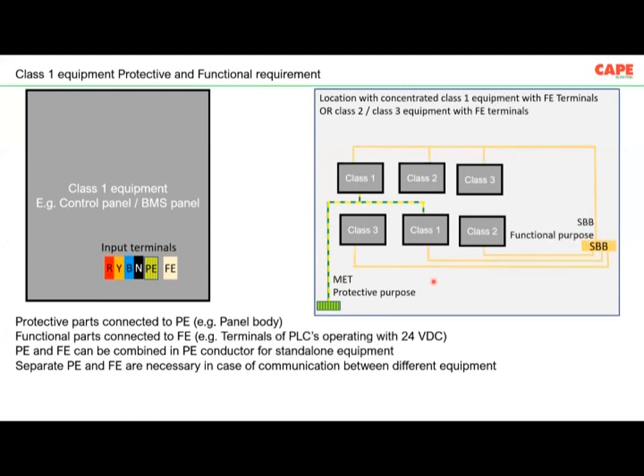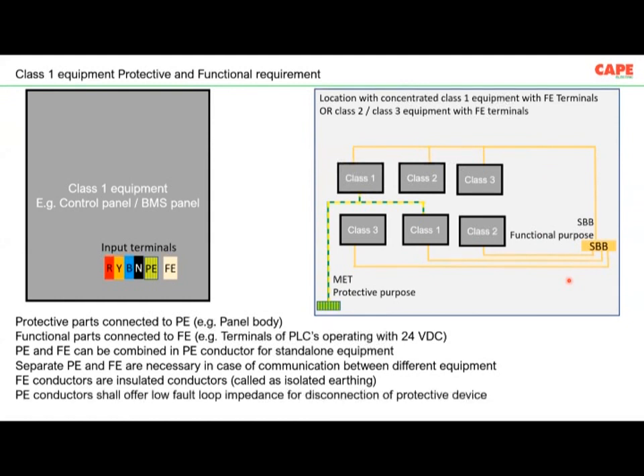Now, what do we do with the FE terminal? The FE terminals of the equipment are connected to the SBB, sub-bonding bar, for functional purpose. The color code specified in the standard is green, and this connection preferably must be isolated, meaning insulated. So you must use insulated conductors for this connection. And there are several other requirements, such as the purpose of the PE conductor is to allow low fault loop impedance for disconnection of the protective device. And functional earthing inside a room is carried out in different topologies called star topology, mesh topology, IBM topology, and so on. I don't want to explain this too much because this is a very technical subject.